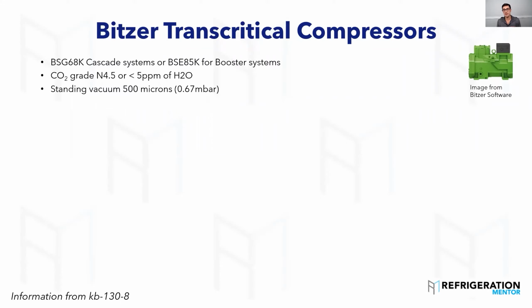It doesn't happen, but you need to try to do your best to follow proper procedures, because if not, you get a store up and running and issues start happening down the road because of that installation. That's mostly what happens, from day one installation. That's when problems arise. So if you don't pull down to below 500 microns or 0.67 millibar, you're going to get moisture into that POE oil, or depending on the oil, this is the BSG, which is a POE type oil, I believe, maybe a PVE, but I'll have to double check that.